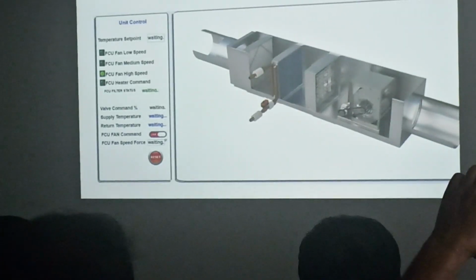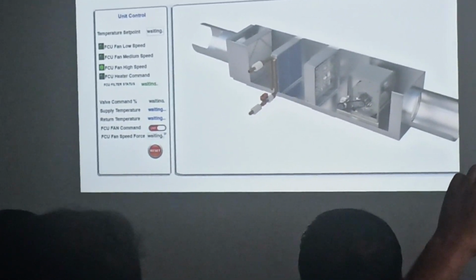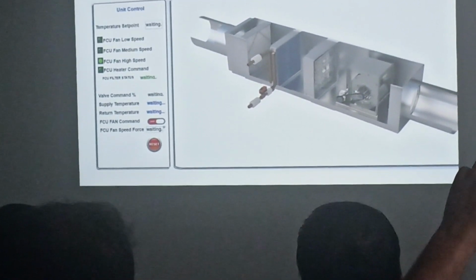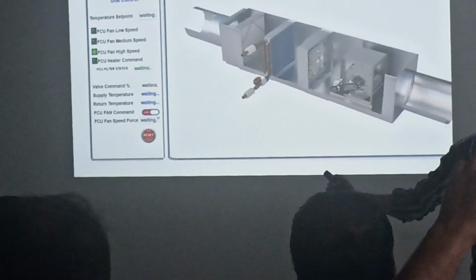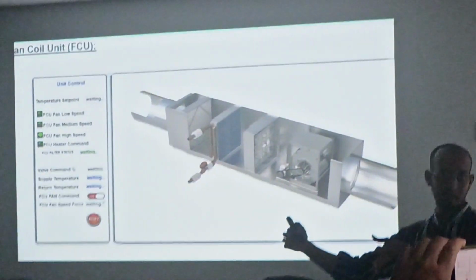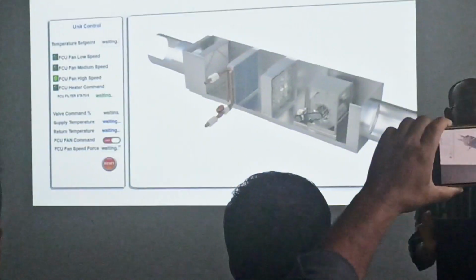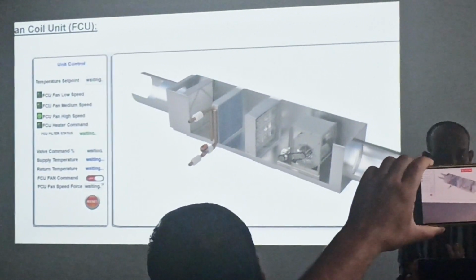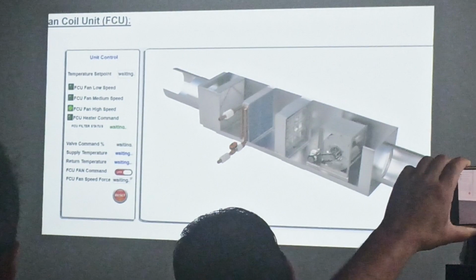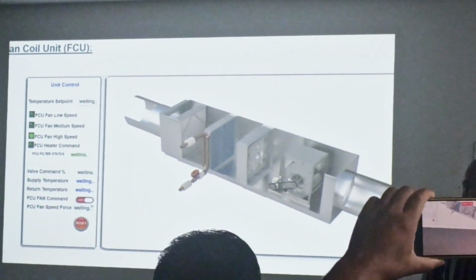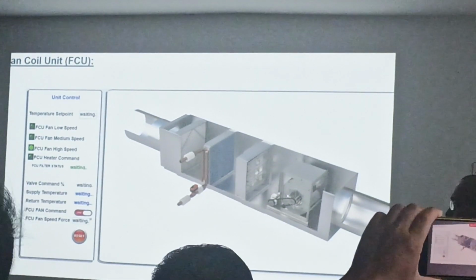One question. Is the SCU connected with BMS? Is the main station BMS workstation connected to the SCU? Each building, for example parcel A, parcel B, where there is an SCU located inside the skywalk, the same building has the workstation. Still there is no centralized workstation in town. Currently the skywalk SCU is not showing on the BMS workstation. In future, maybe, it is still under process.